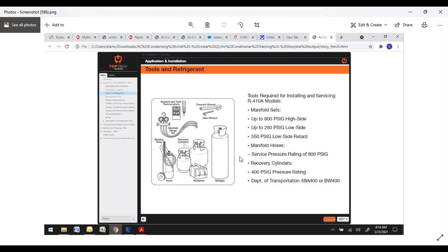It is a good idea to replace your hoses over time. If you've never had one blow up on you, you're lucky. Sounds like a shotgun right off the side of your face. So if your hoses look weak and brittle, get you a new set of hoses because you don't want one of those to bust on you. Recovery cylinders, you do have to have a 400 PSIG pressure rating and DOT transportation 4BA 400 or BW 400.